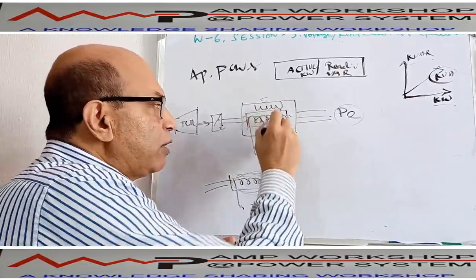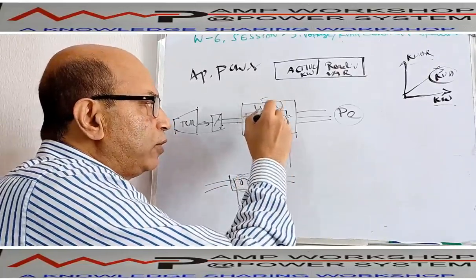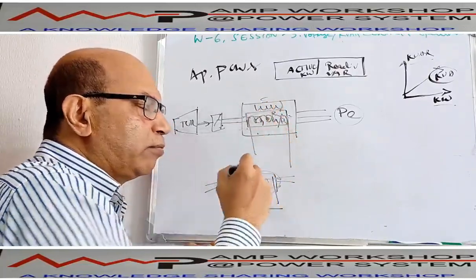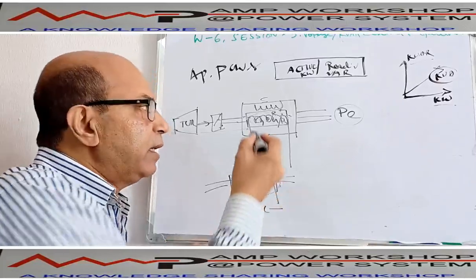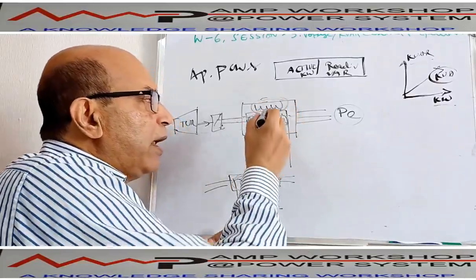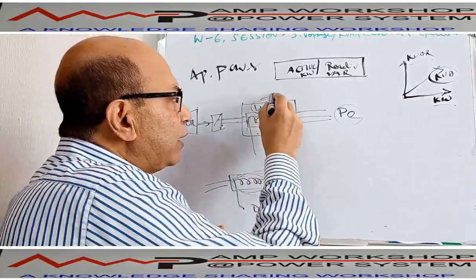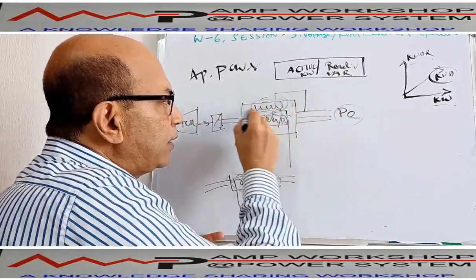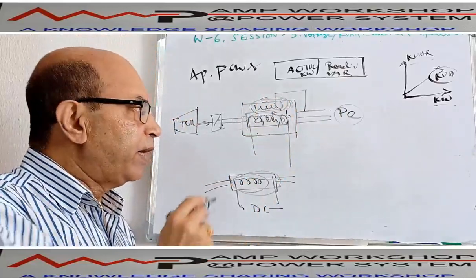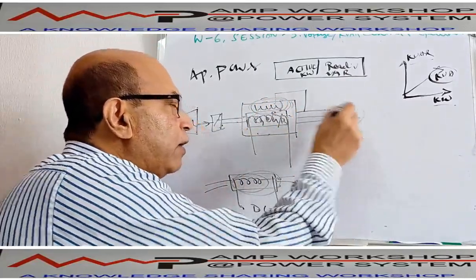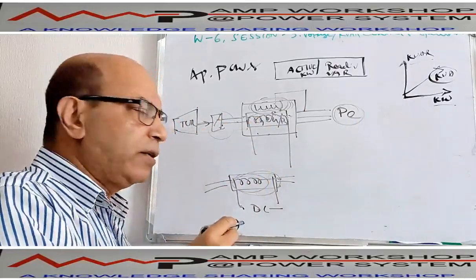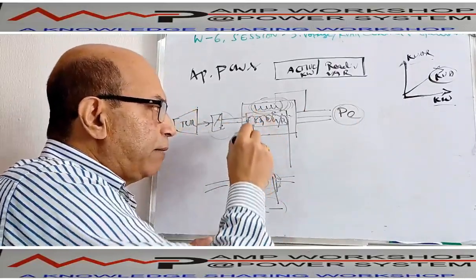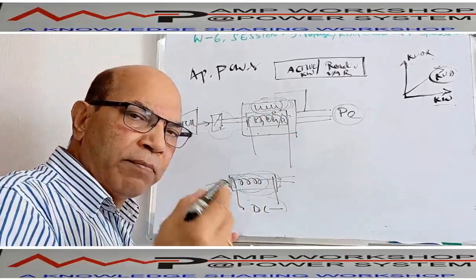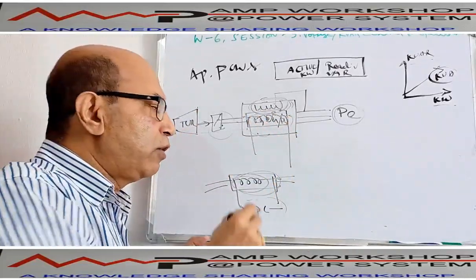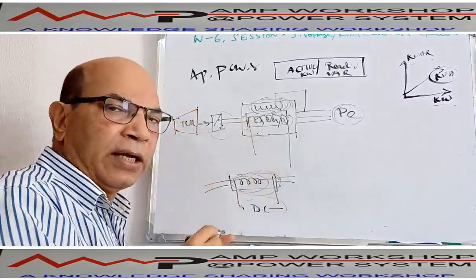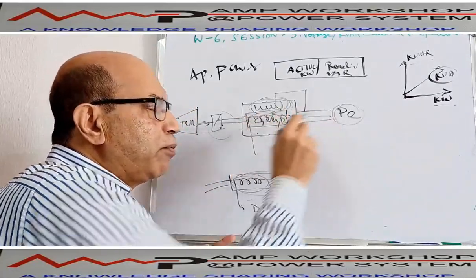This magnet is rotating at 3000 RPM among this coil. When this magnet is moving at 3000 RPM for 50 hertz, there will be an induced EMF in the coil, and due to this induced EMF, it is producing electric power. This power is produced by the armature winding or stator winding. That means when you want to produce electric power, only by rotation you cannot get it. You need some magnet to be rotated, that means the rotor has to be converted to a magnet. Either it could be a permanent magnet or an electromagnet by passing DC current. If we do this, then only it will produce power.